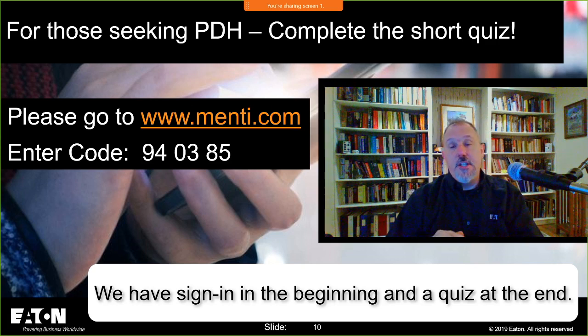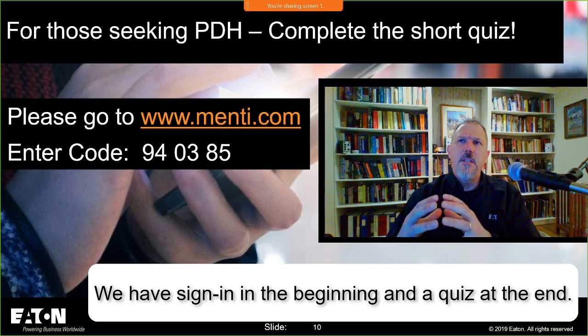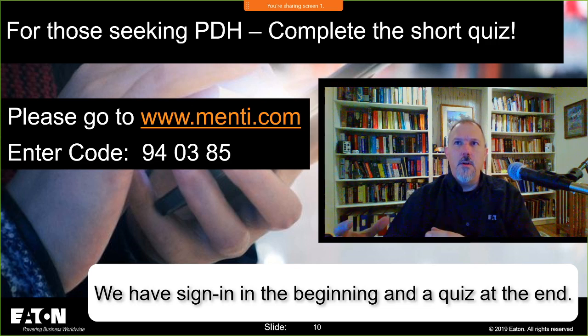It depends on your AHJ. If you have an MCC cubicle with a motor, MCCB (molded case circuit breaker), and motor starter with control wiring feeding a motor, and you remove the motor starter and control wiring, is the MCC cubicle okay to use without a label from a manufacturer?